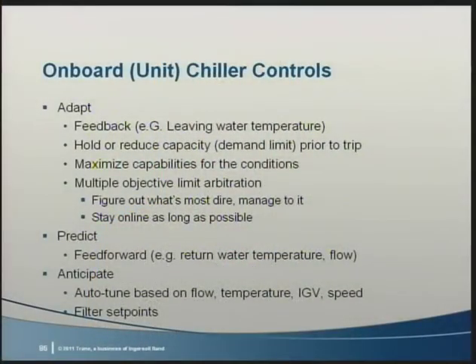But Bonnie, the chiller unit control has to be able to react to the evaporator flow rate changes. Can you tell us a little bit about what has to happen from a unit control standpoint? Sure can, Mick. Just think of your PC. You would not try to run today's applications on a computer that is 10 years old, because even if you could get it to work, you would not have the technical support and parts available. Well, neither should you count on your existing unit controls to be adequate to provide the precision and reaction times needed to optimize your upgrade investments.